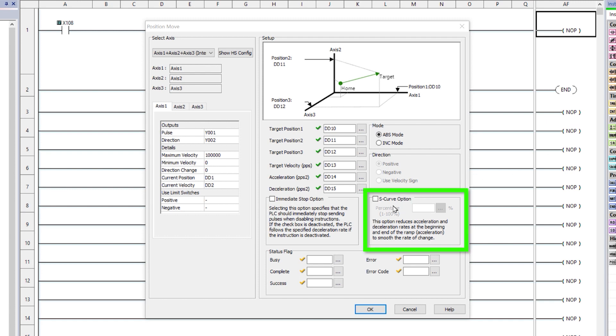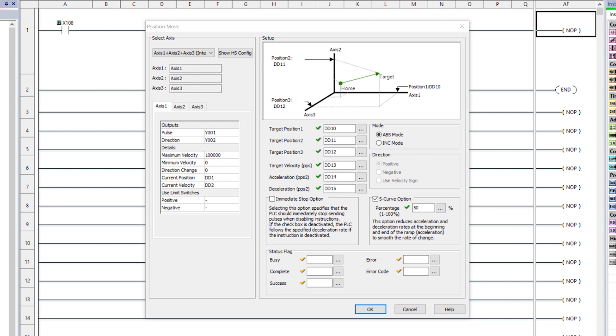This S-curve option will help smooth the transition of the velocity change to reduce jerk and help prevent position loss due to inertia or friction loss. The values range from 0 to 100%.